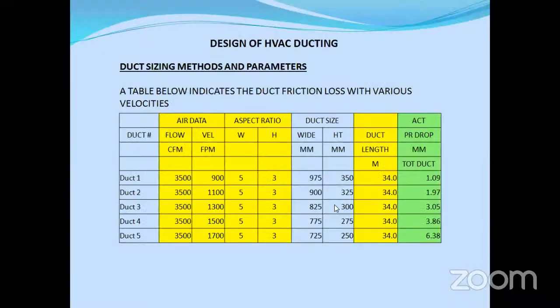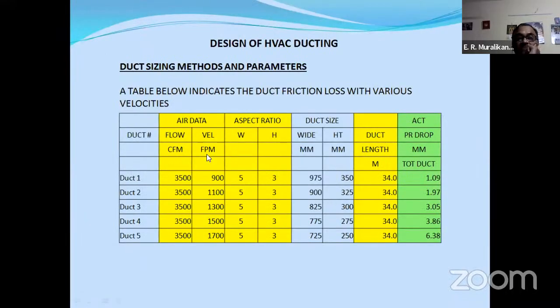So now we just took a comparison of how the friction loss varies with velocities. The Excel, I think people have not understood. When your flow is the same, velocity I am varying, aspect ratio I am fixing, and length I am keeping the same. For same CFM, same aspect ratio, same length, just because of the velocity, the pressure drop of the duct is varying.